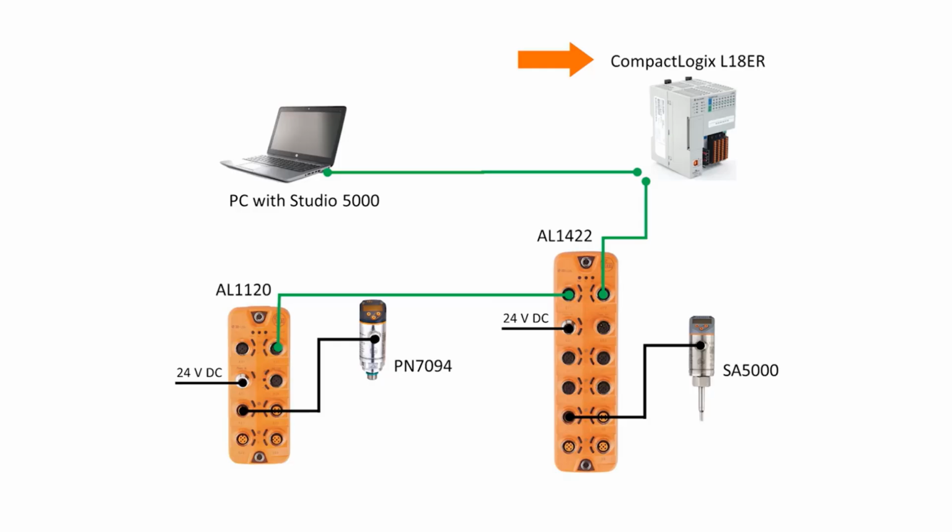In this video, you will see the steps required to set device replacement on an Ethernet IFM AL master through Studio 5000. Please note that using IO-Link always provides you the live process values regardless of the setting. Device replacement is only truly required if you mean to retain parameters such as units shown on the display, color of the display, or in other unique parameter cases.